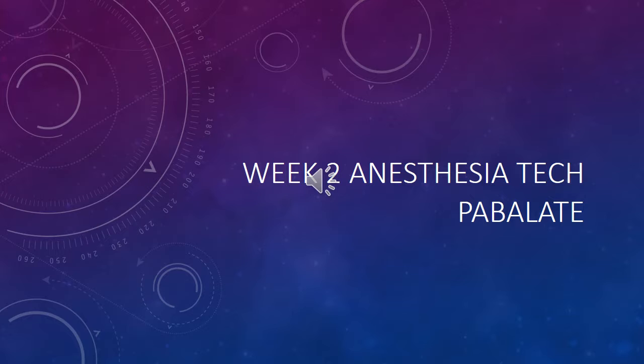So that's the sequence. Unplug the pipeline, wait till the alarm turns on, open the cylinder, and then we're going to close the cylinder and activate the alarm again, which bleeds down the pressure back down to zero, which is our desire, and then we plug back the pipeline, and now we're back into the standard state of the machine. Okay? So that's the supply failure alarm, and then the oxygen failure safety device is an actual audible alarm. Now on the older machines, like a Narcomed or an XL210, it's a pneumatic horn. It sounds like a dying animal. It's unmistakable.